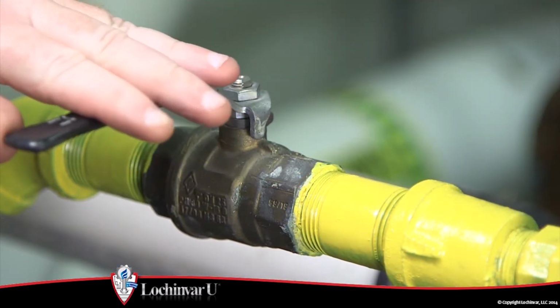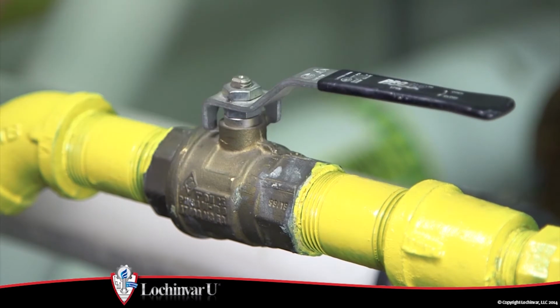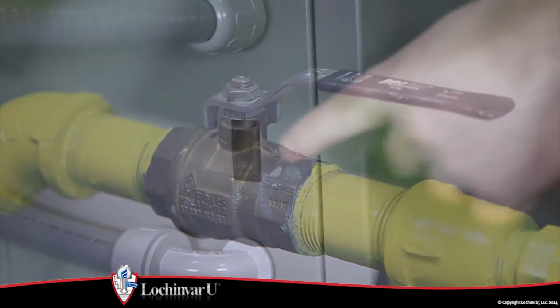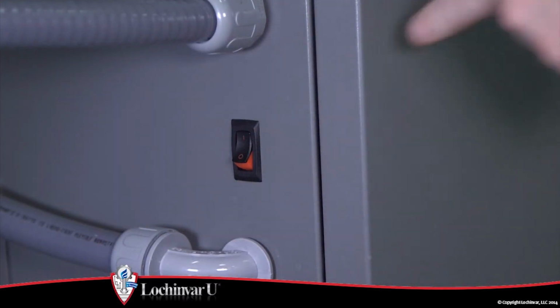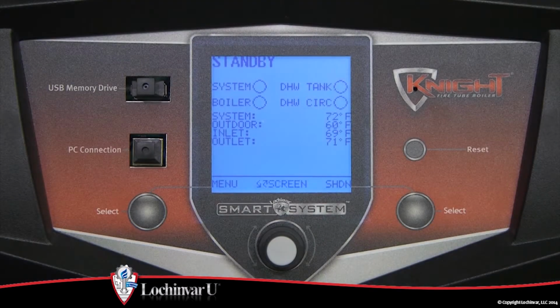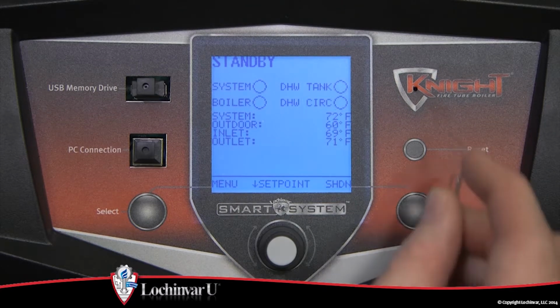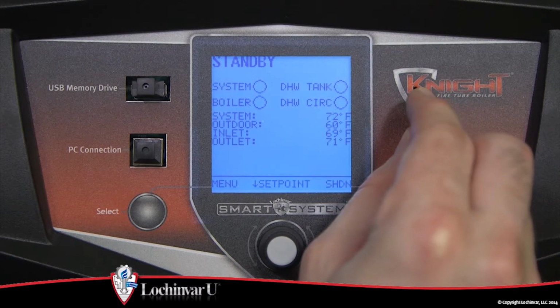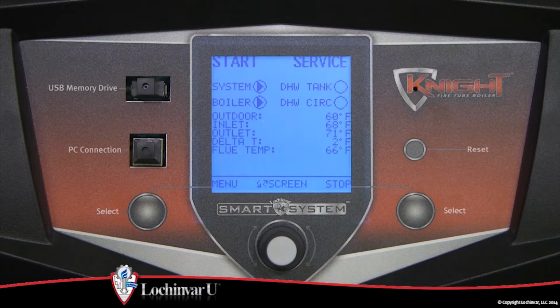Now turn on the main gas supply to the unit at the external main manual gas valve. Turn the on-off switch to the on position. Locate the pinhole button on the display. Using a paperclip or something similar, press and hold the button for 5 seconds. The word service will appear in the status line of the display.